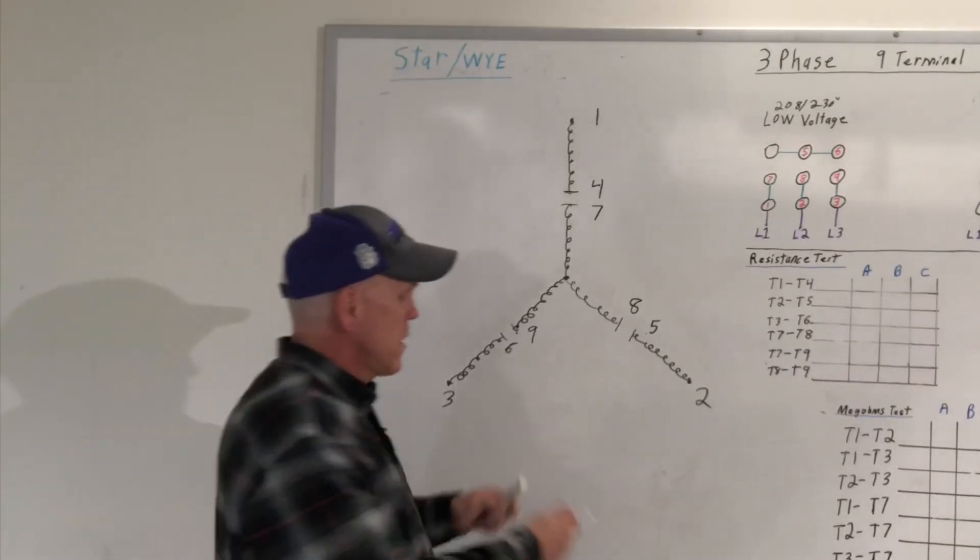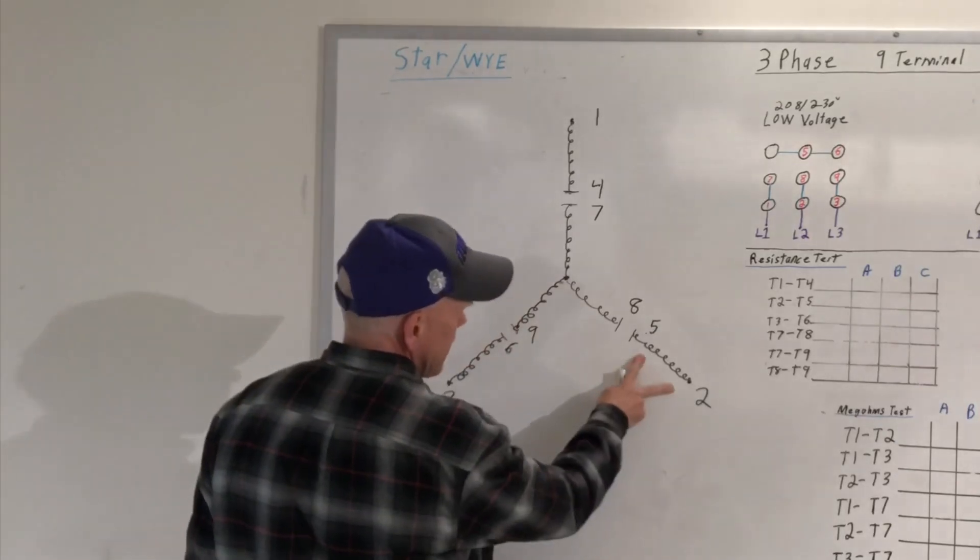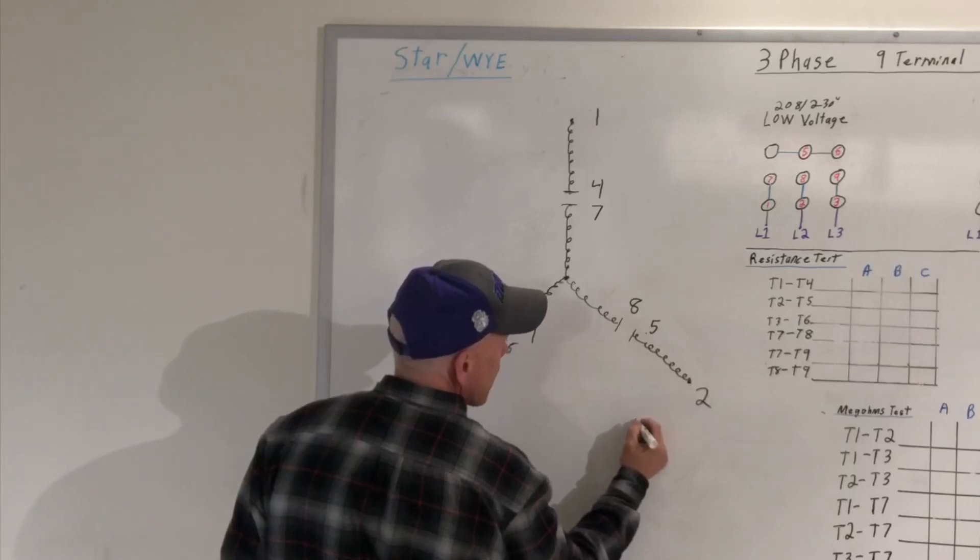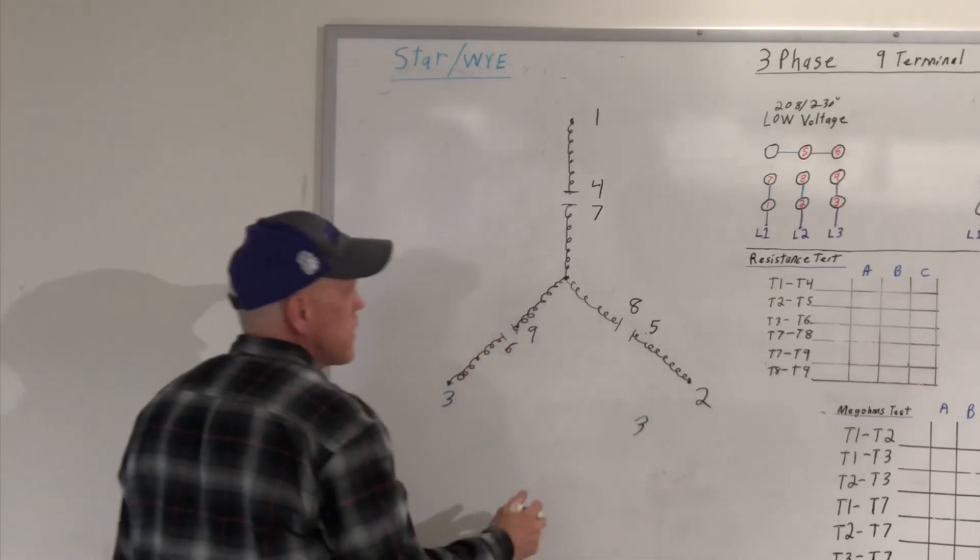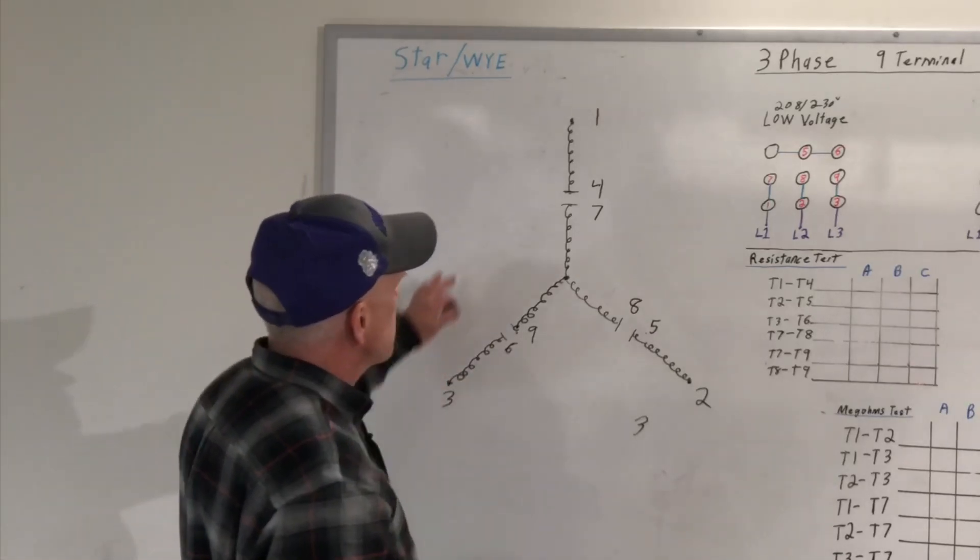When I go up and do an ohm test, let's say for, let's just say that this set of windings is between two and five. Let's just say it may be a three. So I'm looking for a three here. I'm looking for a three here. At least close, within maybe 10% of each other.